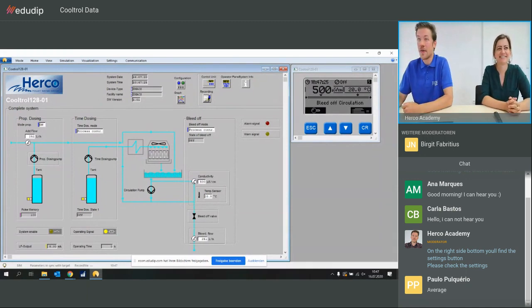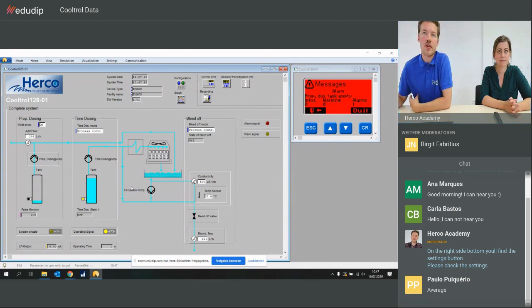All right, exactly. So basically in this display, you see all the information you have from the system. On the left side, we have the two dosing pumps and also the tank. You see the status, so if it's filled or not, right here. In the simulation, we can now simulate that this one is empty. Normally you see on the right side that the screen turns red. This is one of the new things with the Cooltrol. So you actually see from a distance that there's something wrong with the system.